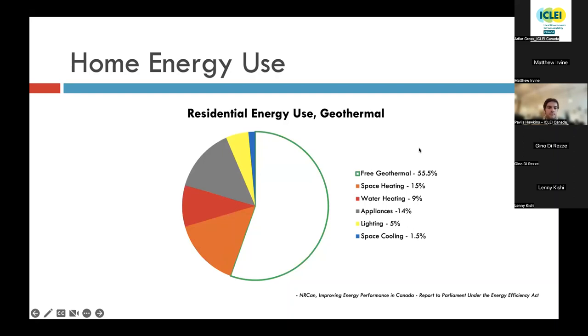That is what geothermal systems do to an energy use profile or a load profile. The space heating reduces from 60% down to 15%, water heating drops from 18 down to 9, and that earth loop outside is providing over 55% of the energy for free into that home. That is fundamentally how geothermal systems are able to offer such high levels of efficiency and such significant energy savings, particularly when you're comparing to propane or oil.